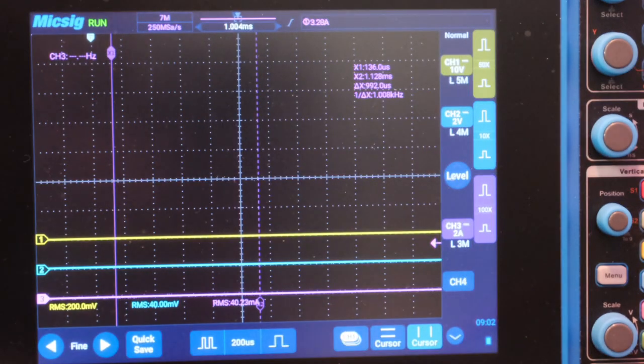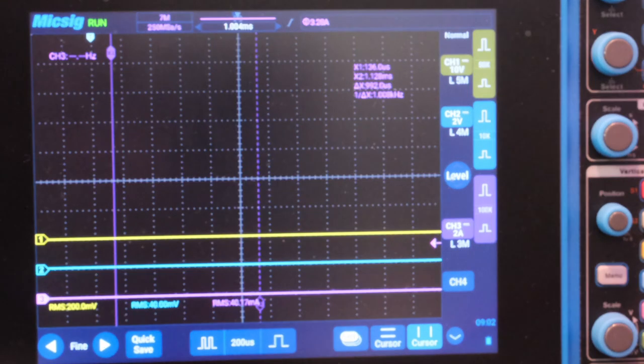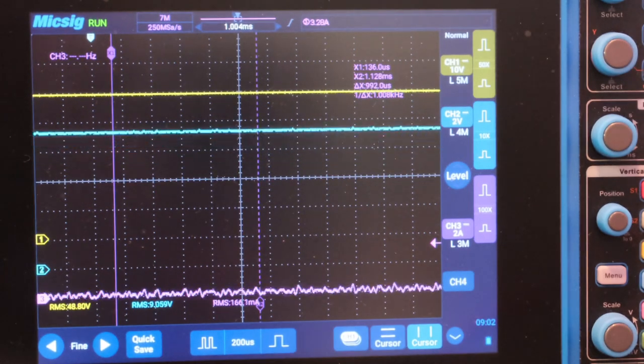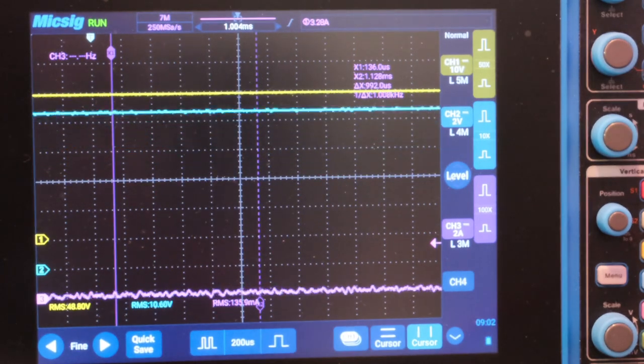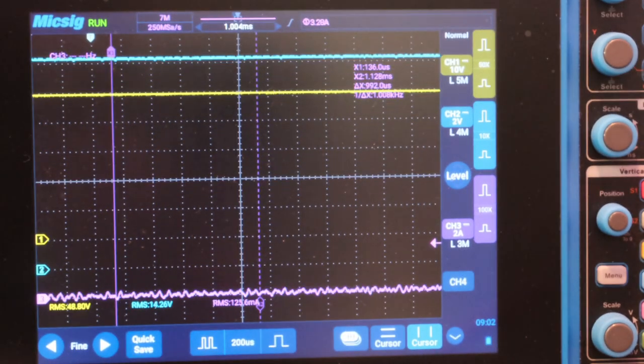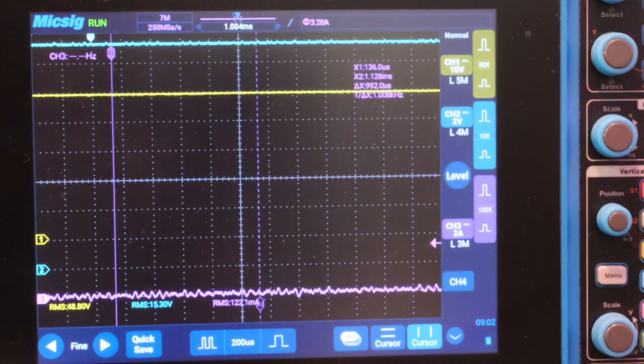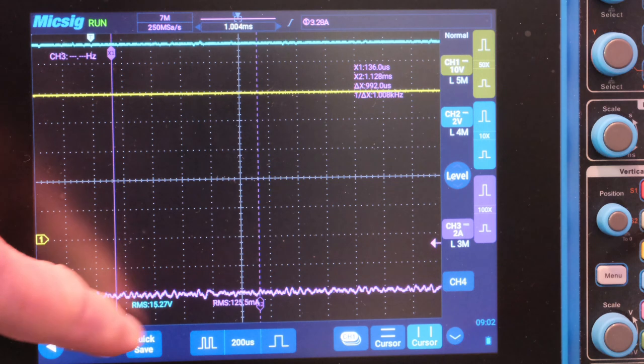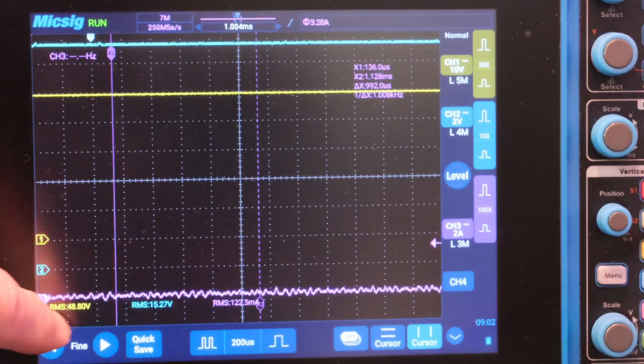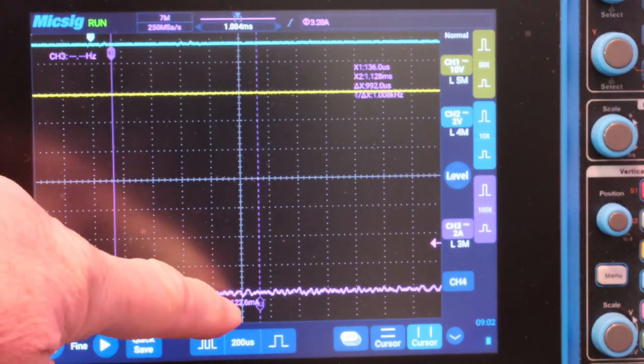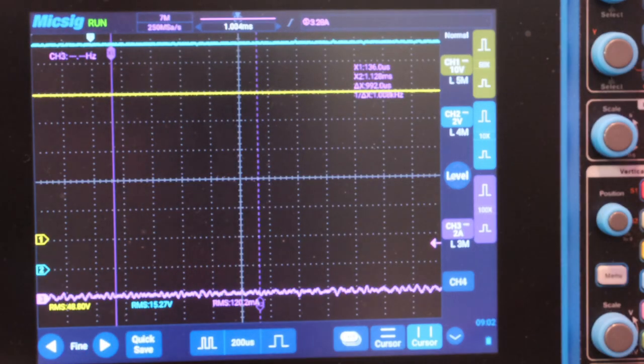Channel one on the MicSig is the output voltage at 10 volts per division — it's going to jump up to about 48 volts. Channel two is the input voltage, which we'll take up to around 14–15 volts. Channel three is the current at 2 amps per division. Let's go ahead and bring up the input voltage. We'll go to 15 volts. Okay, there's 15 volts — a little above at 15.27V. The output is at 48.8V with very little current.